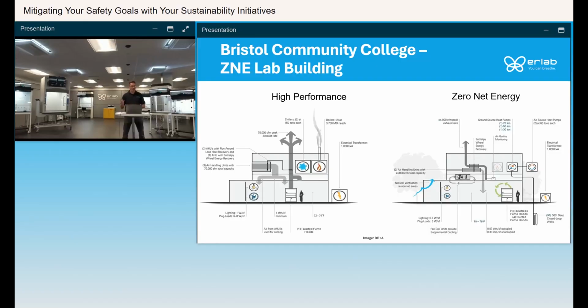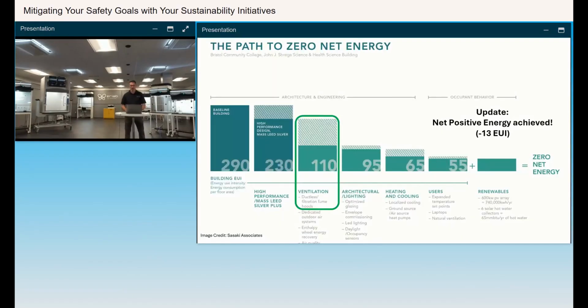That high performance design had 3 air handling units with 70,000 CFM of capacity. With the zero net energy design, with the 13 ductless fume hoods and the 4 ducted fume hoods, they're able to eliminate 1 air handling unit for a total of 2, a capacity of 24,000 CFM, allowing them to reduce their hourly air changes by about 67%.